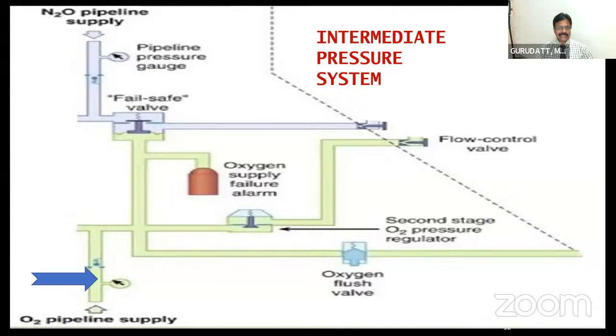The other parts of the intermediate pressure system are the fail-safe valves, the oxygen supply failure alarm, the second stage pressure regulators, and then the oxygen flush valve. So let us discuss these things independently.